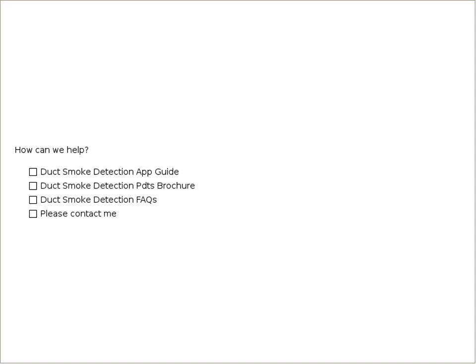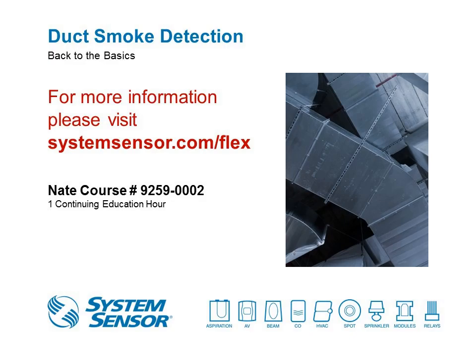If you're doing standard duct detectors, then it's one duct detector to one indicating device. It's a one-to-one ratio. Okay. All right, very good. There are a couple questions around the fire alarm control panel, and the question is maybe an obvious one, but does the fire alarm control panel count as a remote indicator device?